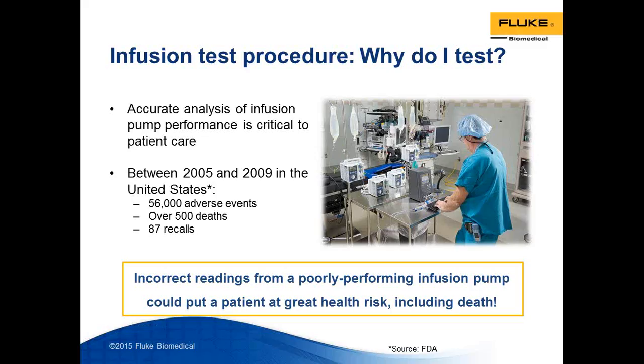So as you know, patient safety is top of mind, right? We all care about our patients, and accurate analysis of infusion pump performance is critical to patient care. We know the emphasis that the FDA has placed on infusion pumps specifically in the last 5 to 7 years. Specifically, if you get into statistics, there have been a lot of incidents associated with infusion pump failures. There was a stat that was released in 2010, which reported 56,000 adverse events, over 500 deaths, and over 87 recalls over a 4-year period.